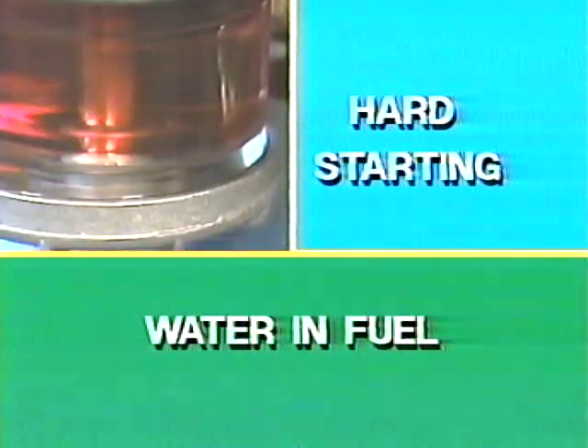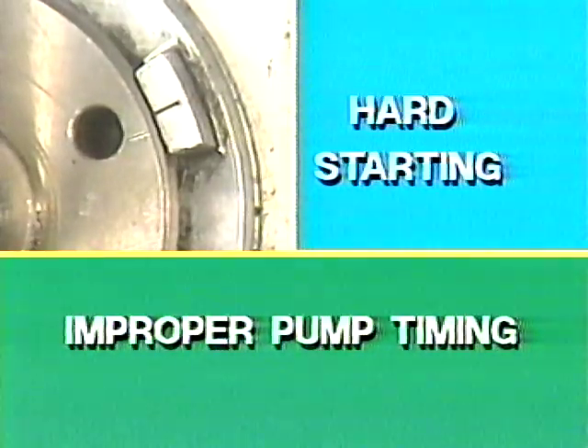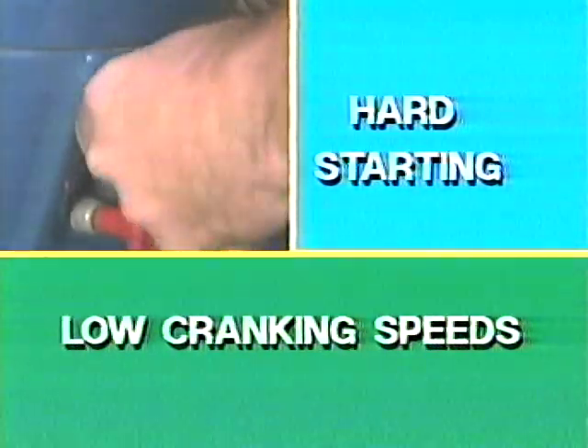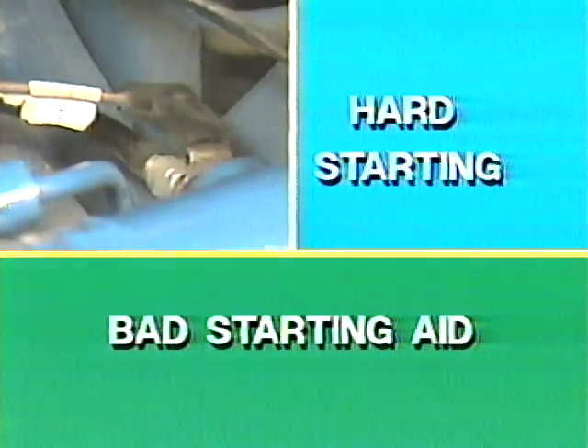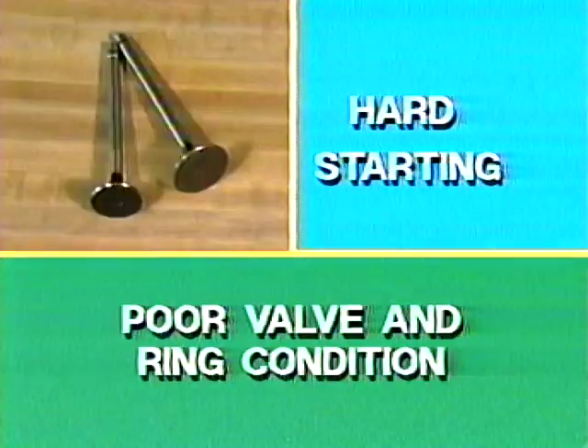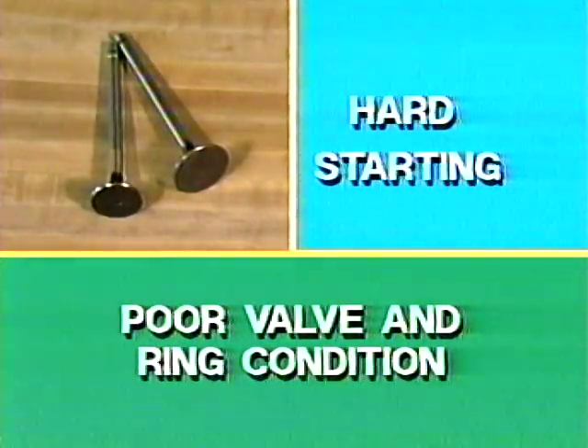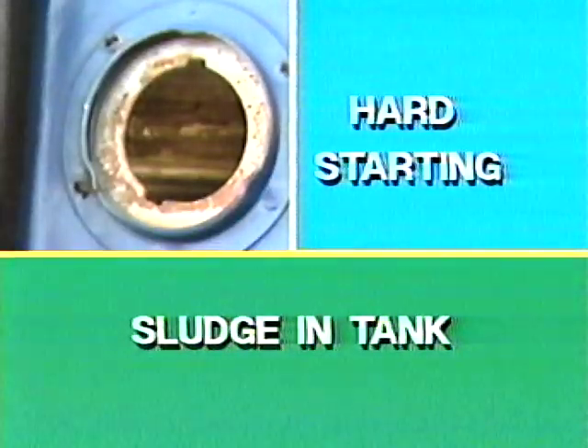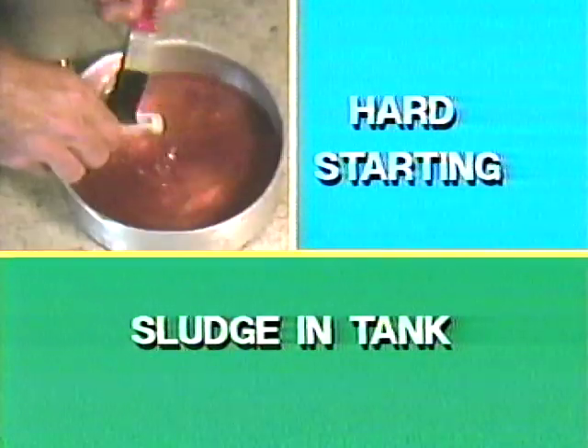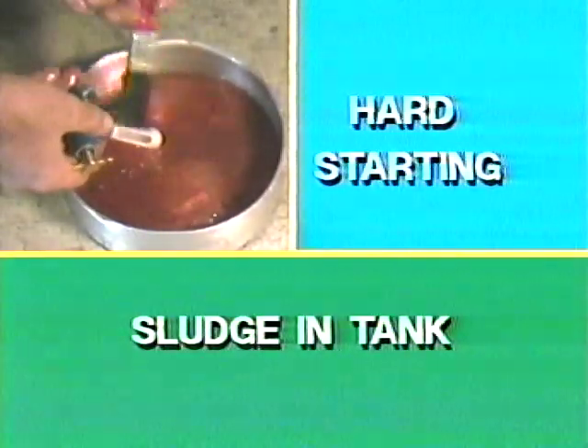When an engine is hard to start, the cause could be a blocked fuel filter, or water in the fuel, or improper pump timing, or low cranking speeds, or a malfunctioning starting aid. There also could be air in the system. The cause may be weak engine compression due to the poor condition of valves or piston rings. Look for sludge in the fuel tank. If sludge is present, drain and clean the fuel tank. If the engine won't start at all, the fuel injector pump may be seized up.